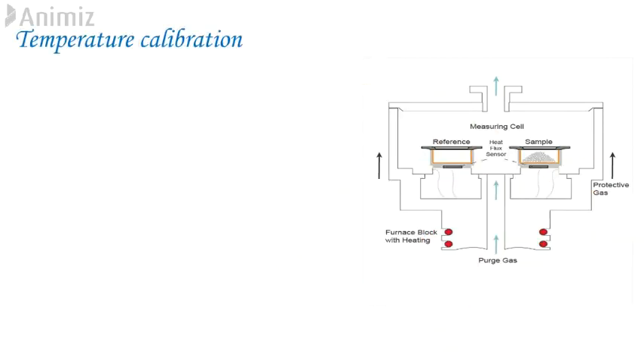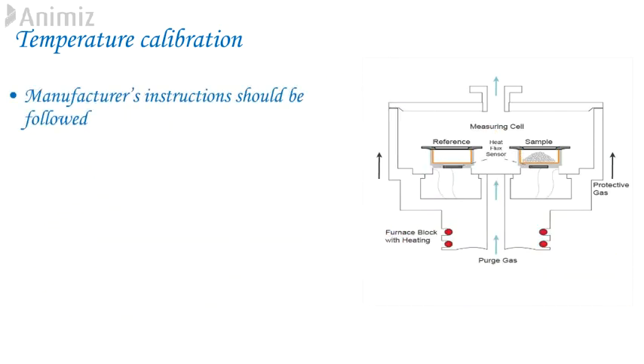2. Temperature Calibration. Calibration needs to be performed prior to analysis to ensure that scan rate of furnace is calibrated. Different instruments use different approaches to calibration and manufacturer's instructions should be followed.